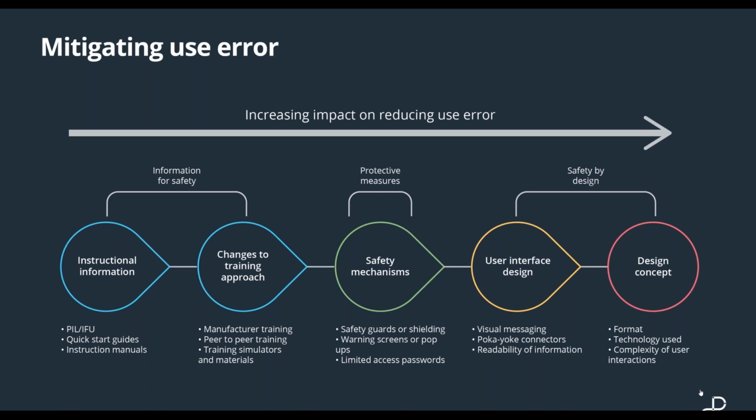However, that's called safety by design, and in that yellow bubble, it's about the design of the user interface. But there's also another level which Louise and I felt wasn't always taken into account within the usability engineering programs at a lot of medical and pharma companies, and that is safety via the design of the concept itself, making the concept inherently safe. It's not just about making the user interface as safe as possible, but taking it up a level.